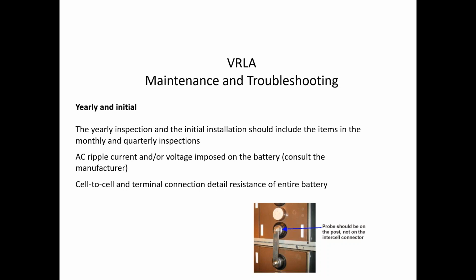And then yearly inspection of the battery should include everything that we talked about before, and also looking at AC ripple current and voltage on the battery. A lot of times that'll be an indicator when the capacitors need to be changed on the rectifier. And there's a rectifier section we'll touch on here too. And then also the cell-to-cell terminal connection resistance that we talked about before.